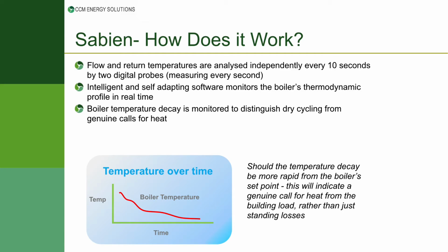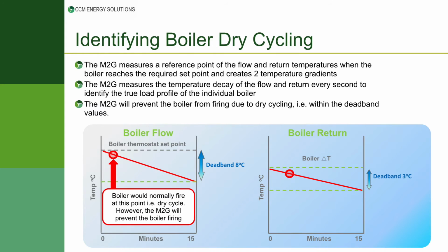So how does the system work? It measures the flow and return temperature. Your existing burner or boiler will measure just the outlet temperature from the boiler, whether that's 75 degrees or 80 degrees. When it reaches that temperature, it turns off. It drops a couple of degrees, and that burner turns straight back on. That's not a genuine load demand. That's just replacing the losses of the boiler through the shell or the jacket or any piping losses.